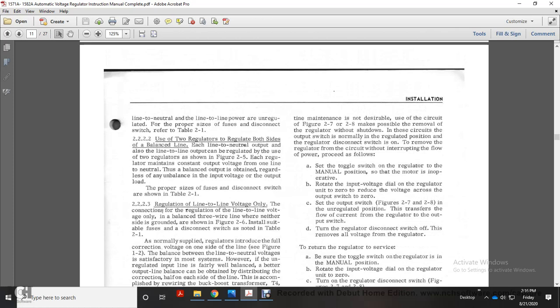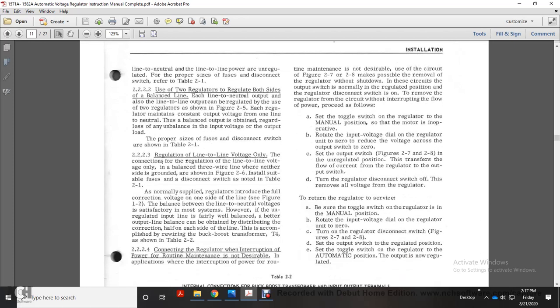Refer to Table 2.1. 2.2.2, use of two regulators with both sides of the balanced line. Each line-to-neutral output of this line can be regulated by either of the two regulators just shown in Figure 2.5. Each regulator maintains a constant output voltage, one line to neutral. Thus a balanced output is obtained, retained, even with an unbalanced input voltage. The size of the fuses and disconnect switch is shown in Table 2.1.